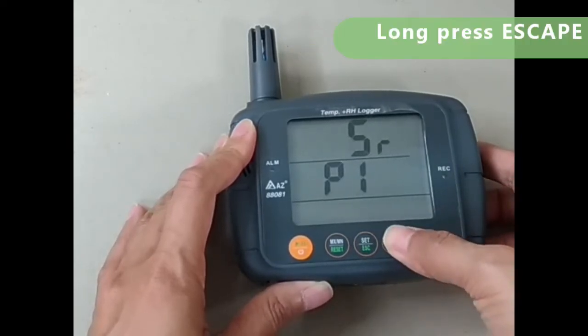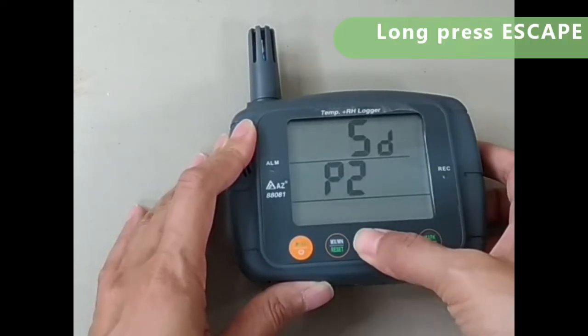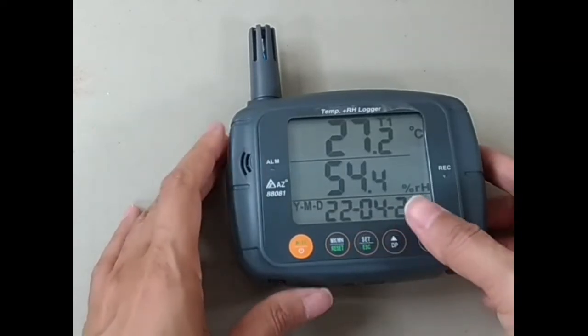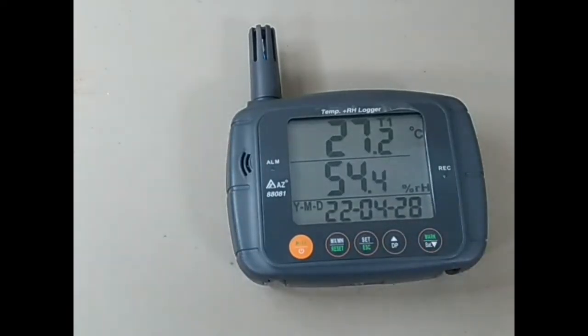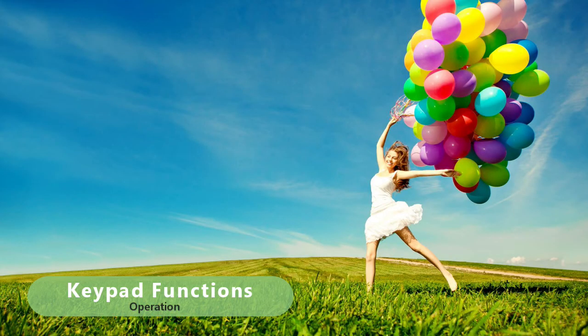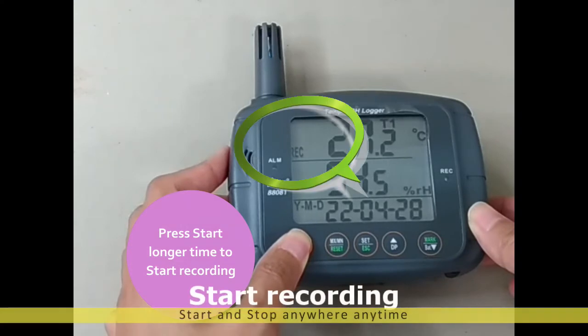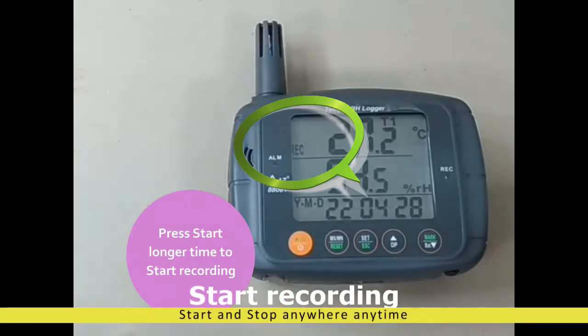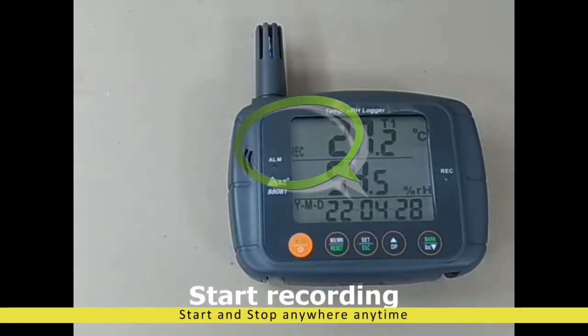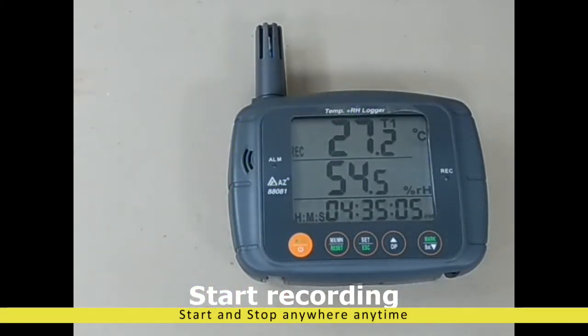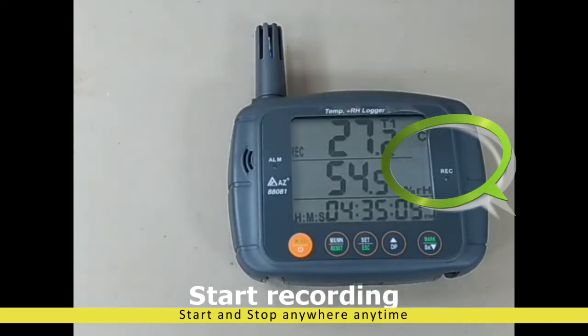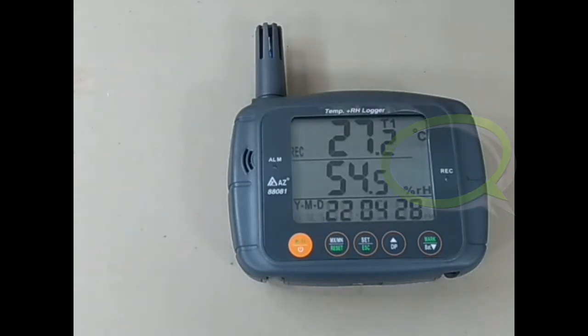After setting, press escape key longer time to quit. Leave the logger in any place where you want to record the temperature and humidity. Press start button for 2 seconds till rec icon appears on display and green LED blinks. The green LED will blink every 10 seconds.